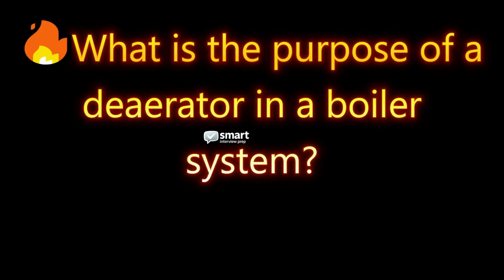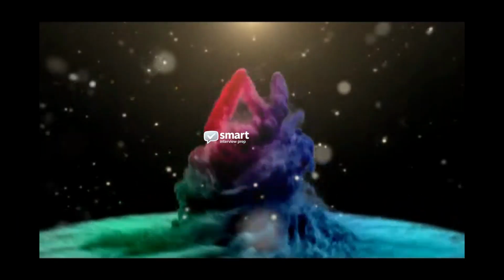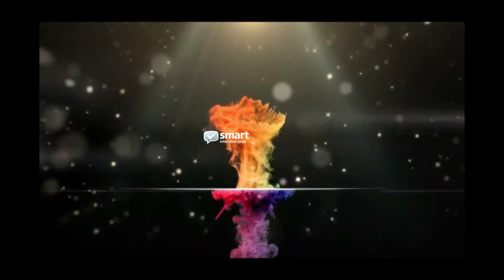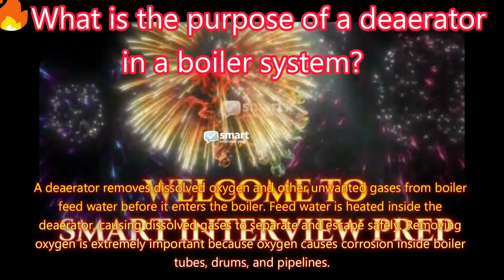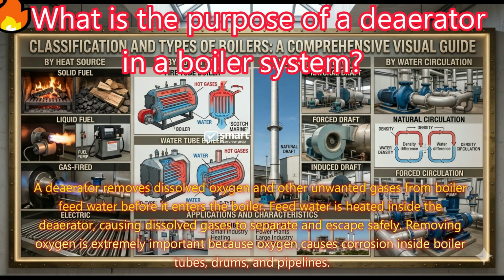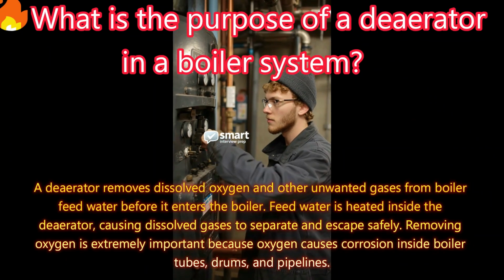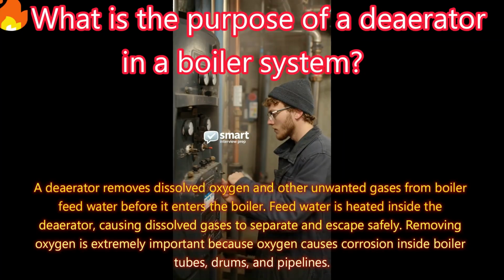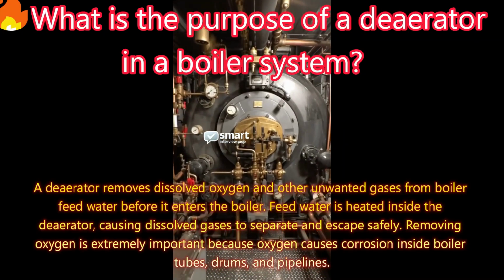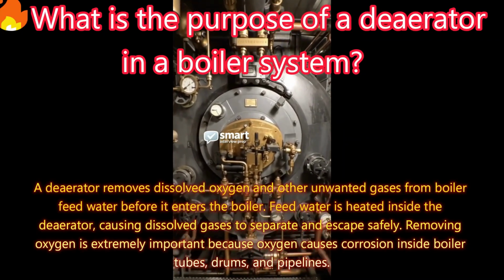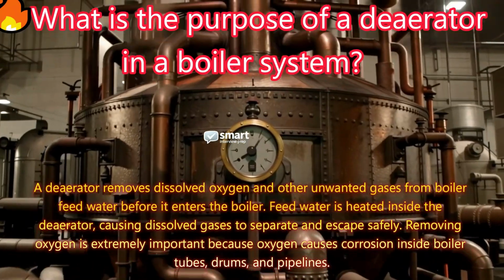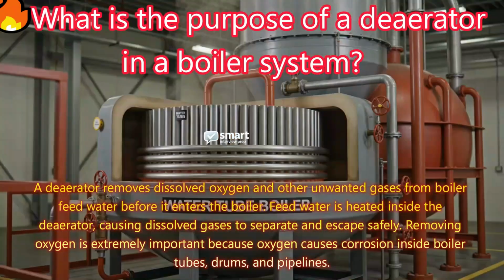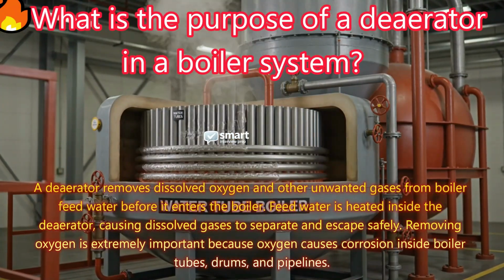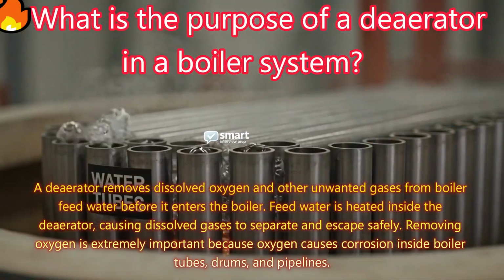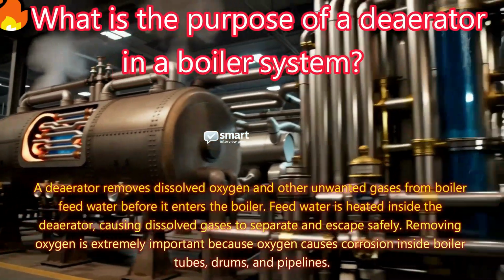What is the purpose of a deaerator in a boiler system? Answer. A deaerator removes dissolved oxygen and other unwanted gases from boiler feed water before it enters the boiler. Feed water is heated inside the deaerator, causing dissolved gases to separate and escape safely. Removing oxygen is extremely important because oxygen causes corrosion inside boiler tubes, drums, and pipelines.